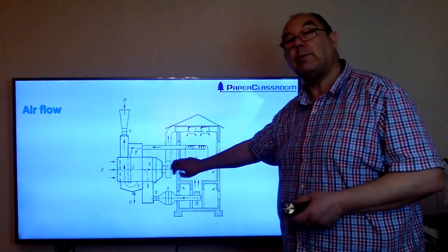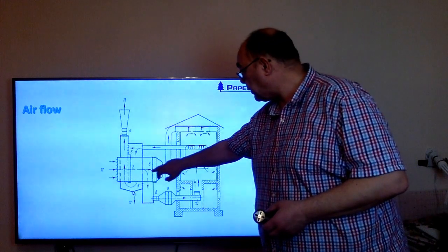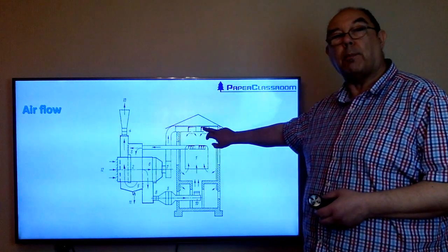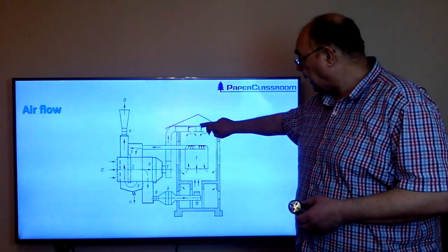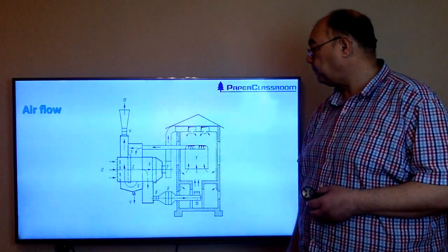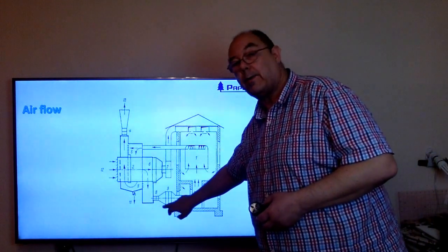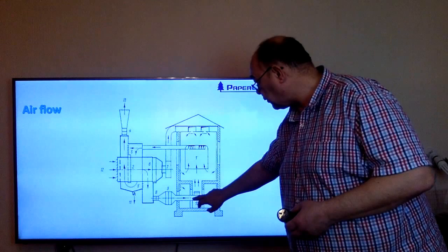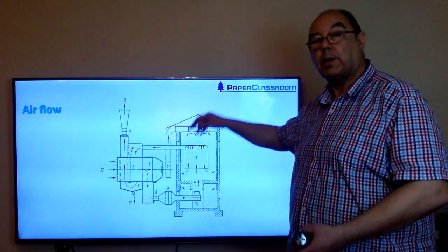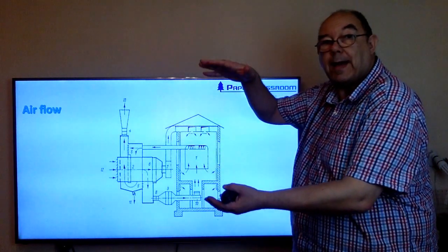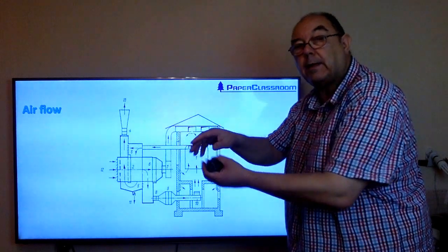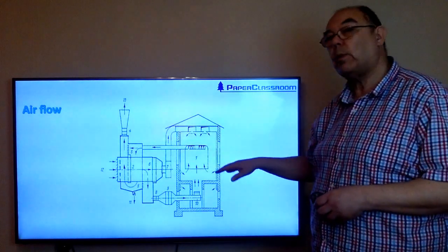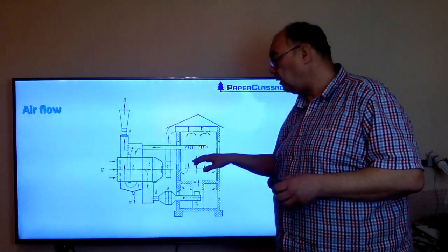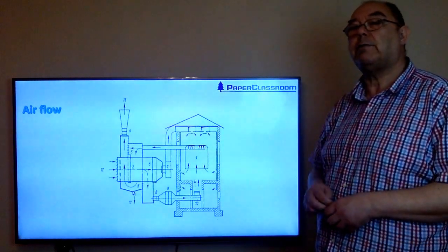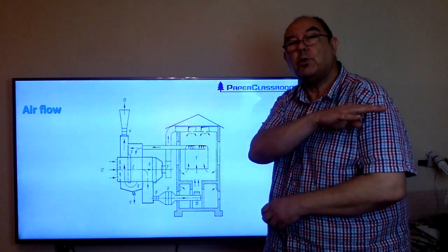The air that comes in, we do two things with it. We bring some of it in to the top of the dry system and we push air down, and we bring other air in and we take it to the bottom and we push it up. So we've got these two streams of air coming down and meeting. The point at which they meet we call the 0 point, and on most machine configurations 0 point is usually somewhere around shoulder height.